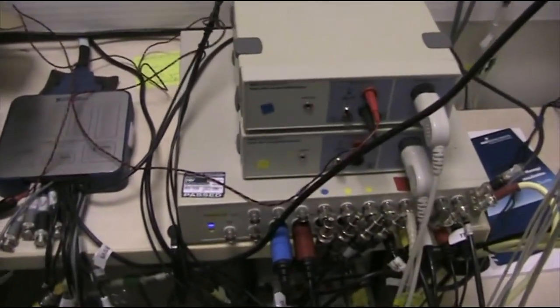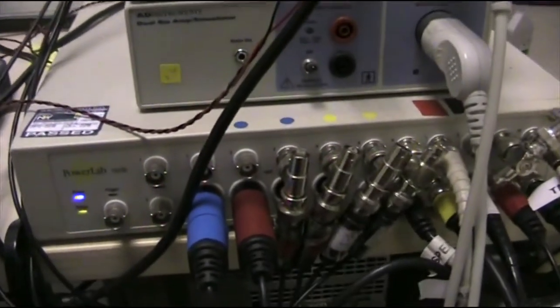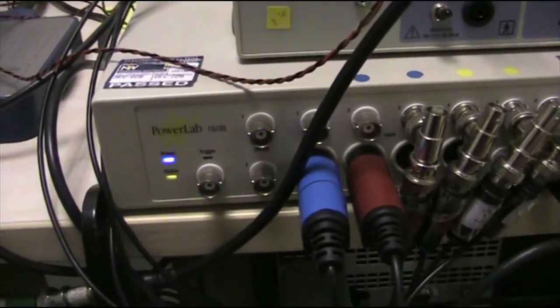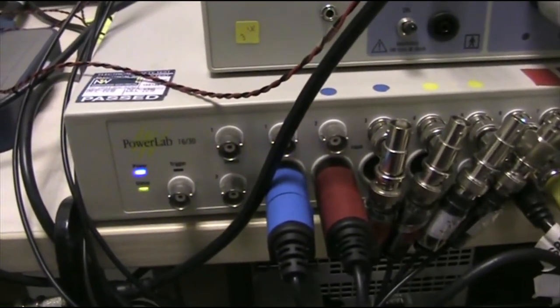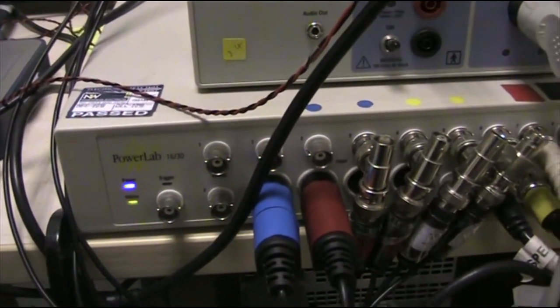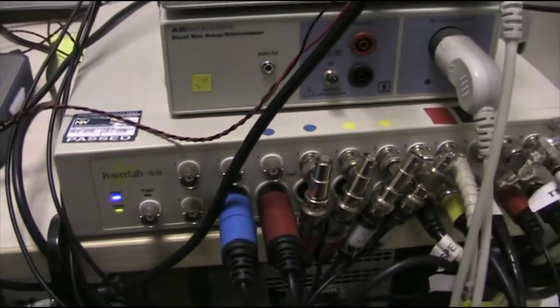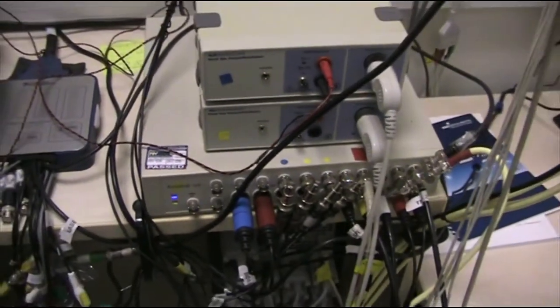To turn the PowerLab on, press the switch at the back on the left. It will whir and flash for a few seconds, and then a solid blue and solid yellowy-green light show when it's ready. Do not use the box if the lights are flashing.